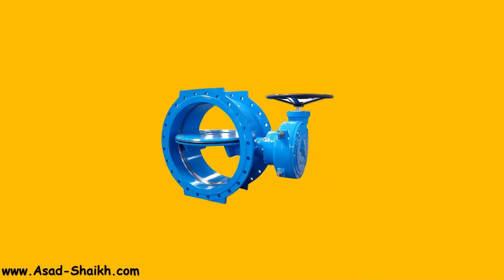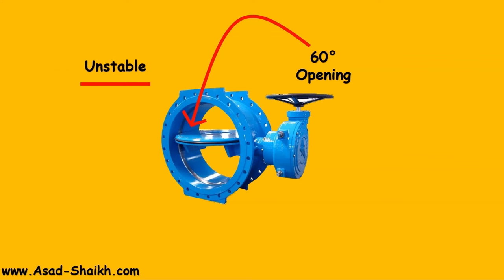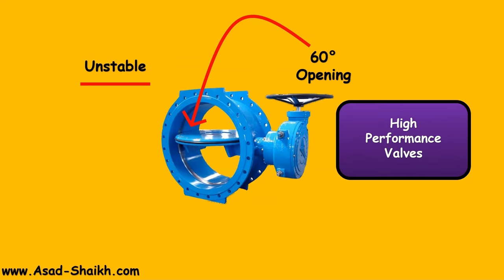If you see here, if it opens at 90 degrees completely, you will have the complete flow passing through it. But if the opening goes to 60 degrees, here a conventional butterfly valve used to be unstable. If that is the case, and you want to control your flow in this range of operation, then generally the latest technology valves, such as high performance valves, have to be selected, which have a higher cost. It also has to be confirmed with the vendor from whom you're procuring that the valve will be sufficiently able to control flow at that degree of operation.